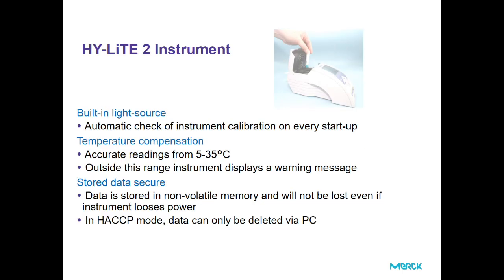Our HY-LiTE 2 luminometer is a very robust instrument with specific features and benefits. First, it has a built-in light source, which is used for automated instrument calibration on every startup. It means when you switch on the instrument, it automatically calibrates the photomultiplier against the built-in light source. You don't need any separate calibration procedure or calibration tools.